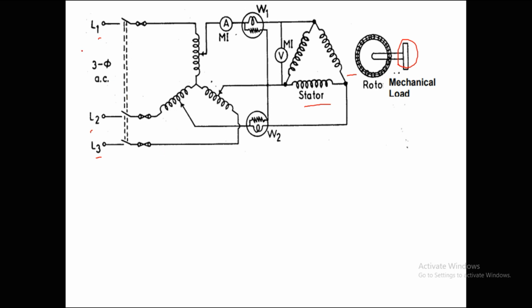And remember, we have to maintain rated voltage and frequency throughout the operation while performing this load test. While performing the load test, we have to measure the amount of current entering the machine, because the load test is purely based on the value of the rated current.